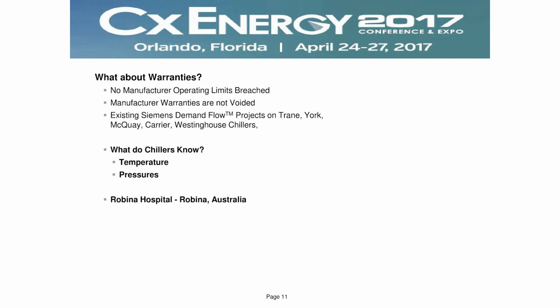Let's move on. One of the questions that generally comes up is, what about warranties on the equipment? I tell you, about 4 years ago when we introduced this overseas, internationally, I was responsible for that. Every country we went to, and it didn't matter what the manufacturer was, Trane, Carrier, York, Century, Mitsubishi, all said the same thing. You cannot vary the flow of water through our chillers. It will ruin the machines, it will void the warranty. You pull out their own engineering manual and it shows you what the min and the max flows are for every one of those machines. And you say, explain this to me. Well, they can't. We went through that in 2008 and 2009 when we introduced this in the US as well.